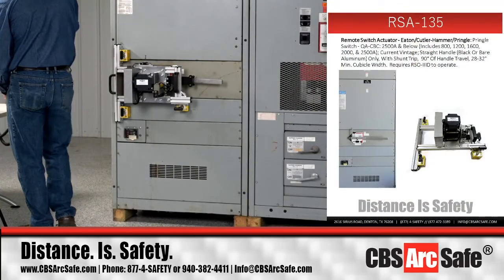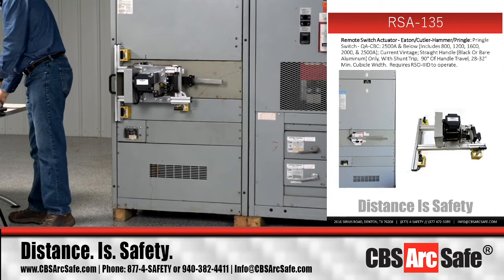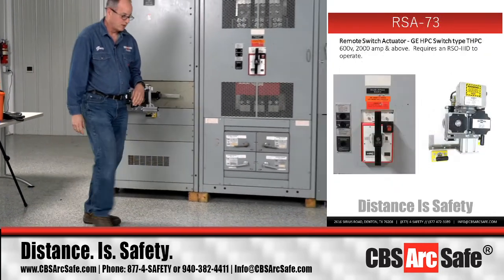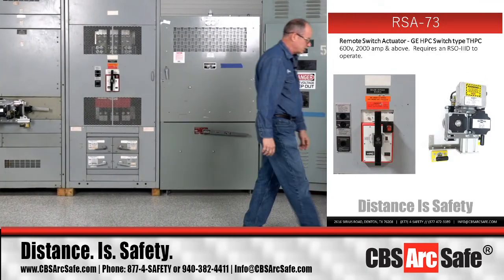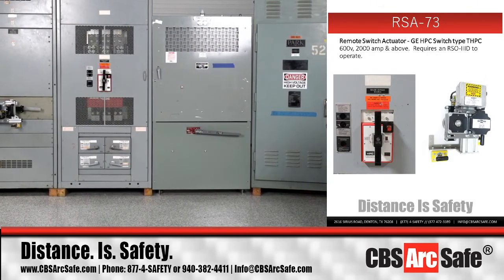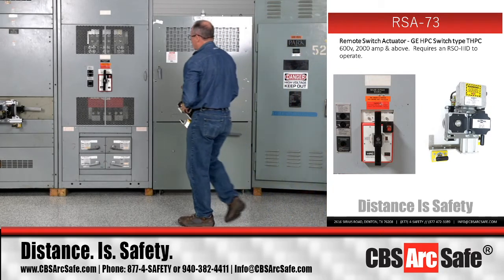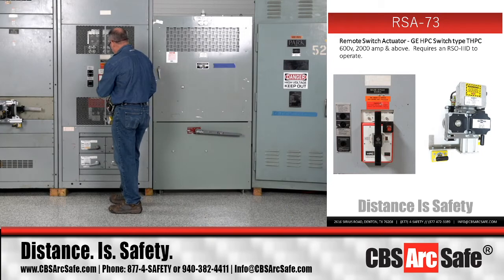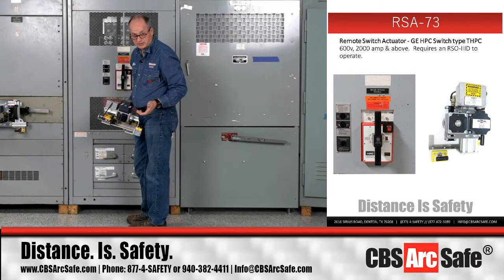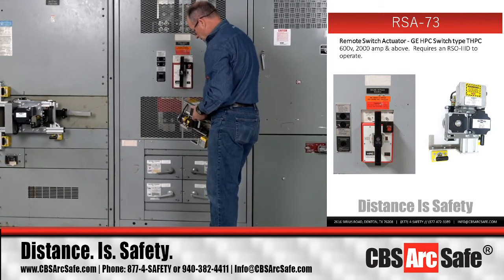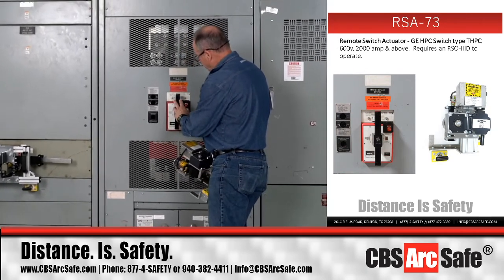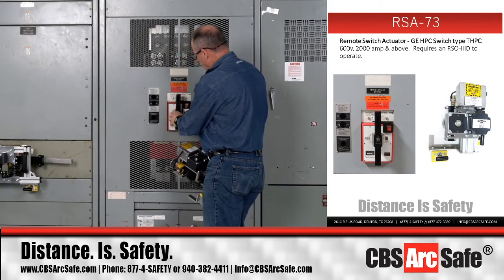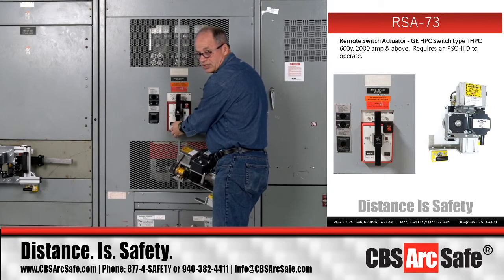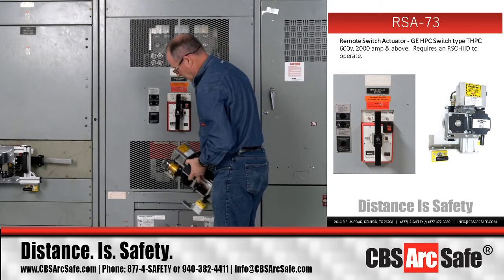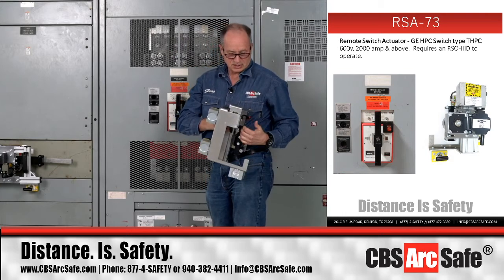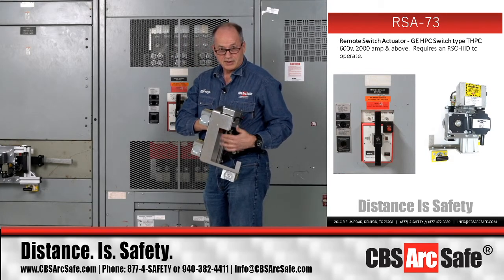Now, for the next actuator, the General Electric HPC, we're going to use the RSA 73, which comes in 2 sizes. The GE switches are basically 2,000, or I think 2,500 amps and above, and this is a 3,000 amp switch we're going to be dealing with today. The difference is they're both labeled HPC or THPC. The lower amperage frame has just a single handle instead of a double handle. So this is what it looks like on this side. This is going to operate the handle, and this is going to operate our trip.